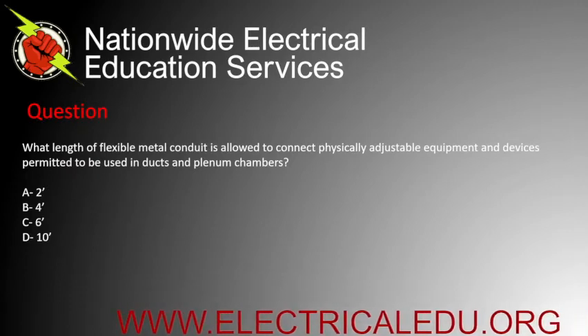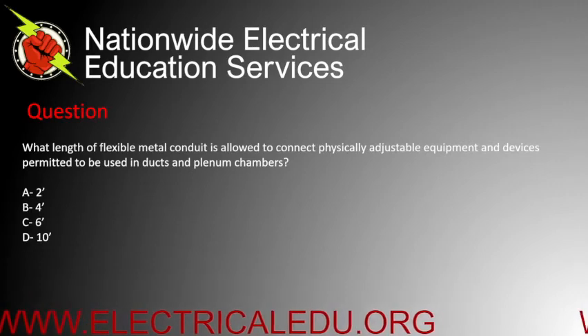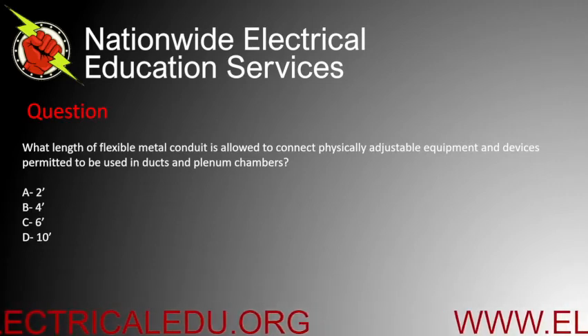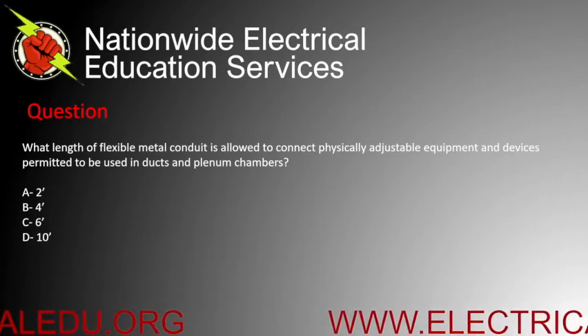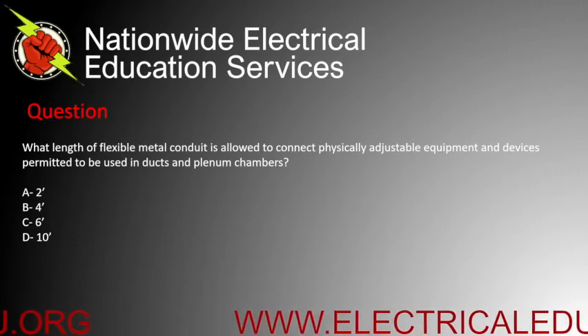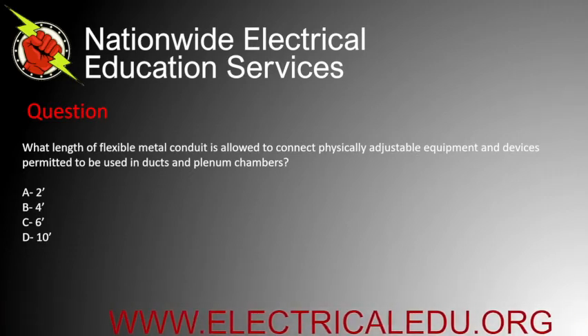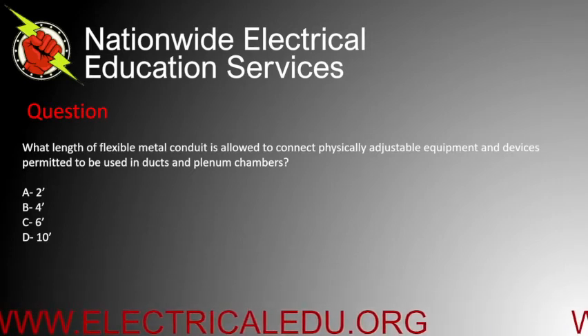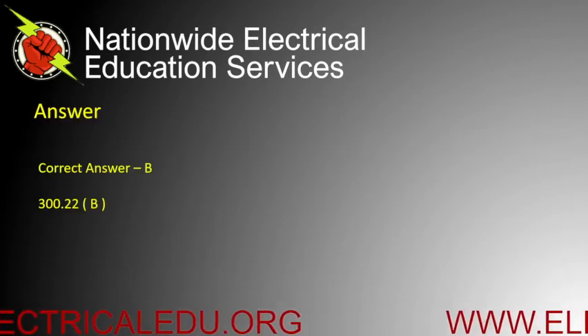What length of flexible metal conduit is allowed to connect physically adjustable equipment and devices permitted to be used in ducts and plenum chambers? A) 2 feet, B) 4 feet, C) 6 feet, or D) 10 feet. Correct answer is B.